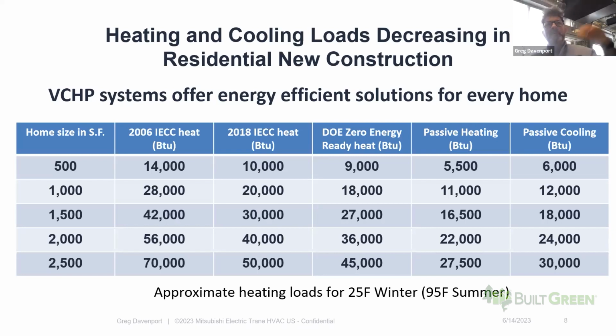Another important thing is that heating loads get lower and lower as you build a better envelope. Cooling loads are partially driven by outdoor air temperature and partially by internal gains — cooking, human beings, lighting, computers, bathing, hot water, and things like that. So in Washington State, heating loads are getting lower and lower as we build better, but cooling loads are not coming down as much. We're starting to see more homes where cooling is close to heating, and in some projects with glass facing south or west, cooling loads may actually be higher than heating loads. That's a big change in terms of how we have to do HVAC design.